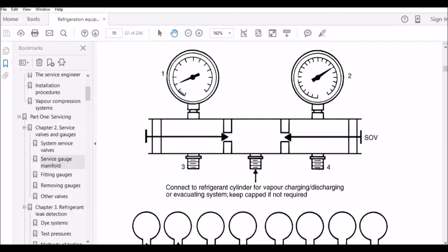And then number 4 is representing the service port, whereby the refrigerant from the high side. So your red hose line is connected to the refrigerant from the high side. Okay. And the purpose of this diagram is to show you that, say our blue hose is connected to the low side connection here. Once you have the blue hose connected to the low side connection, once there is pressure in that blue hose, it goes straight to the gauge.